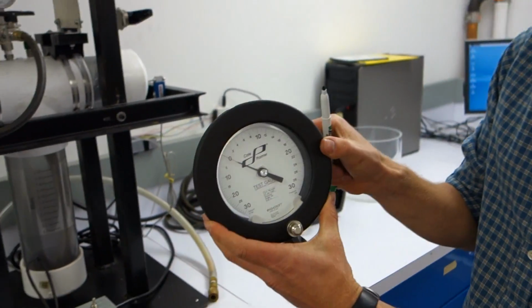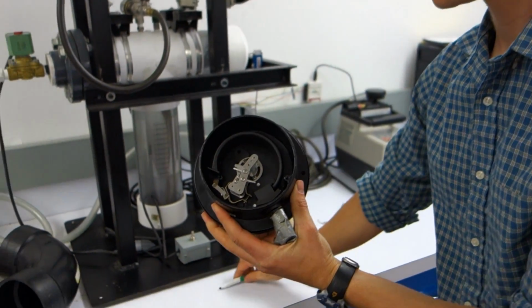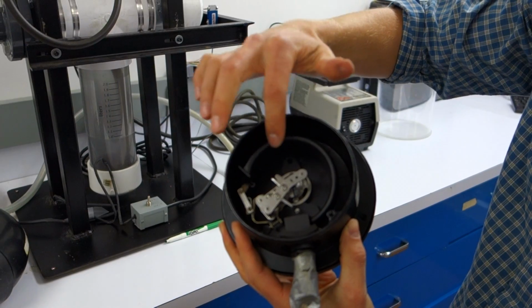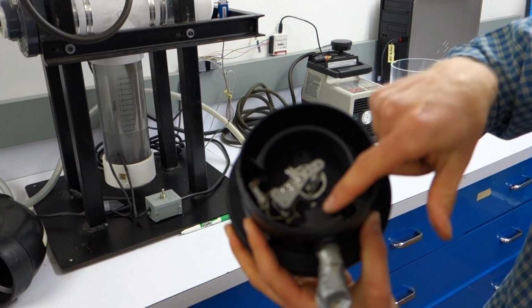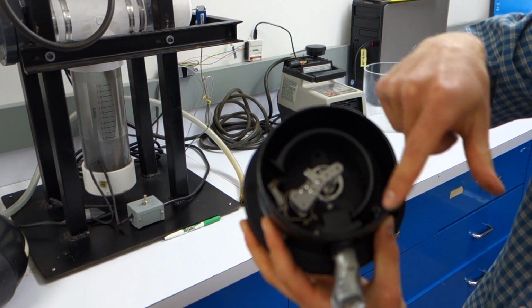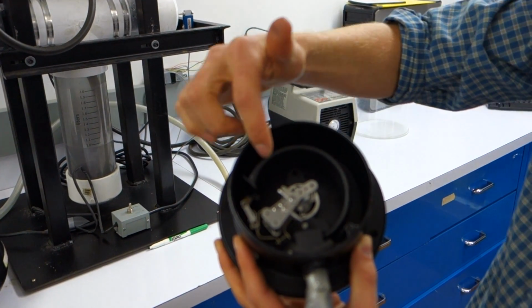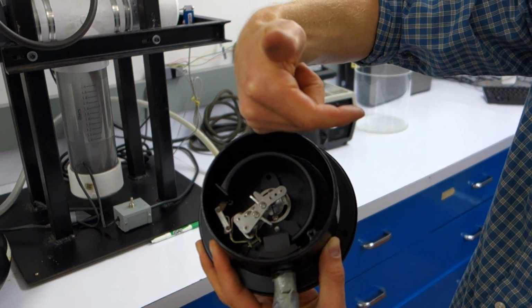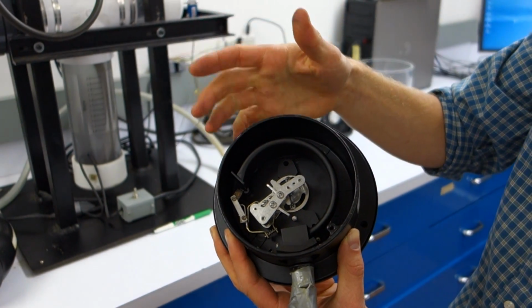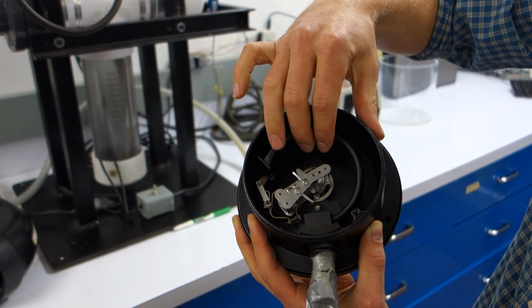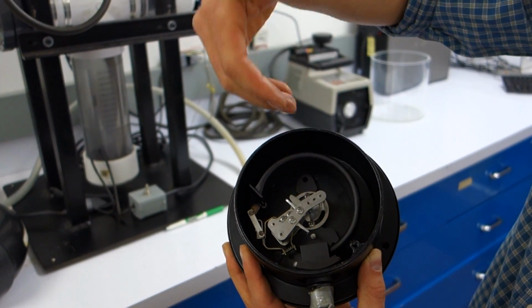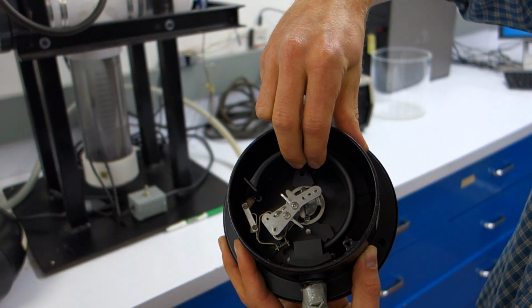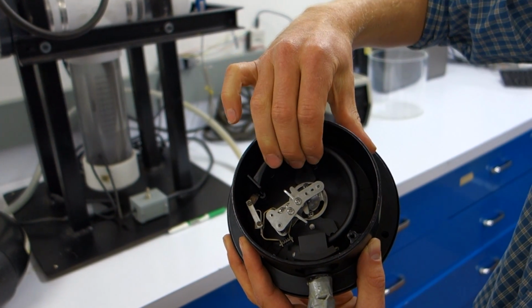You'll notice, so we've got one here, we're going to look at the backside. You'll notice there is a flexure here, an element which is hollow inside, which is flexible. The interior of this is exposed to the same pressure as in our reservoir tank we want to measure. And the amount of surface area exposed in this direction is greater than the amount of surface area exposed in this direction. Since pressure acts isotropically, the net force on this element, since there's more surface area exposed in this direction, is going to unfold this flexure.